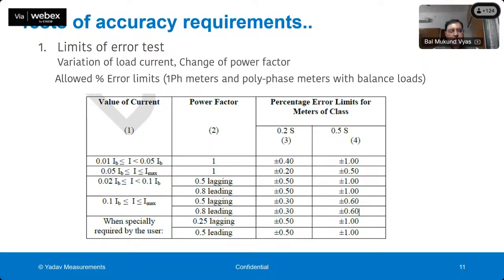While testing the meter, the current is varying, the power factor is varying, and the accuracy against the reference meter is tested. The reference meter used should be traceable to national and international standards, and it should be at least 5 times more accurate. So if we are doing accuracy testing or calibration of a class 0.2 S meter, then the overall uncertainty of measurement should be better than 0.04%.